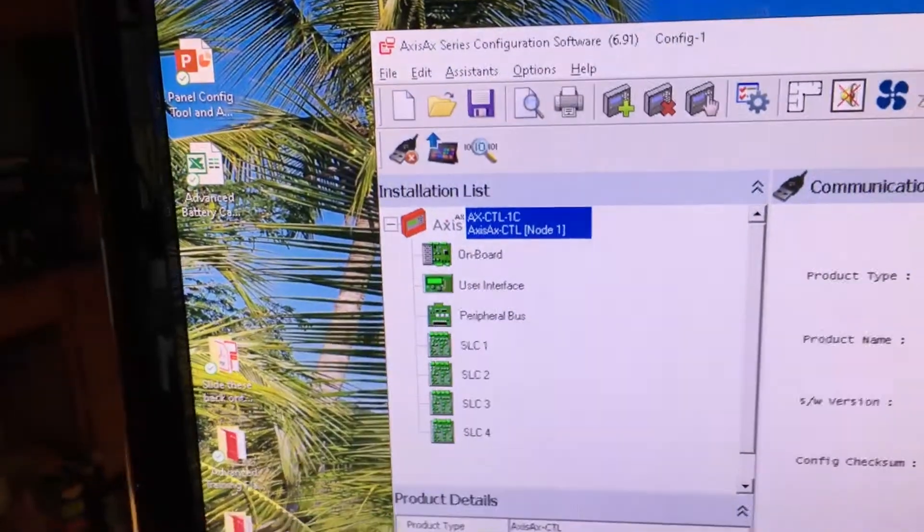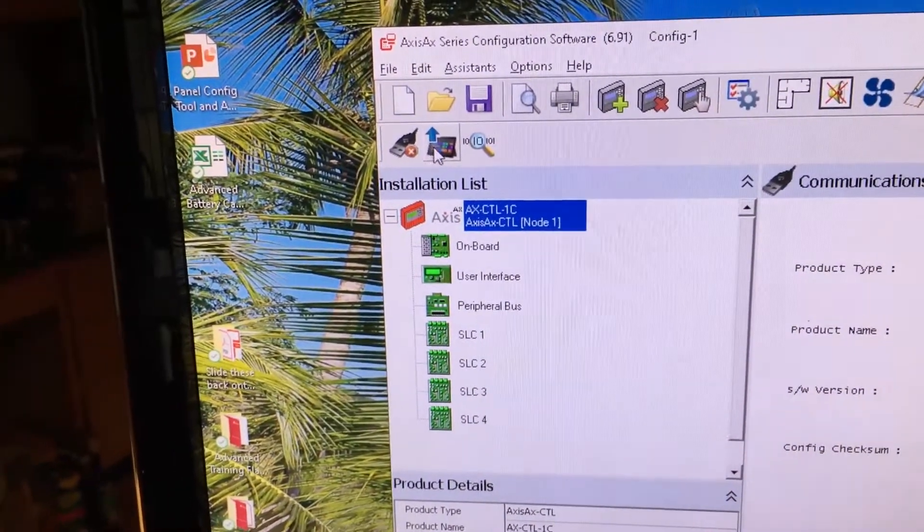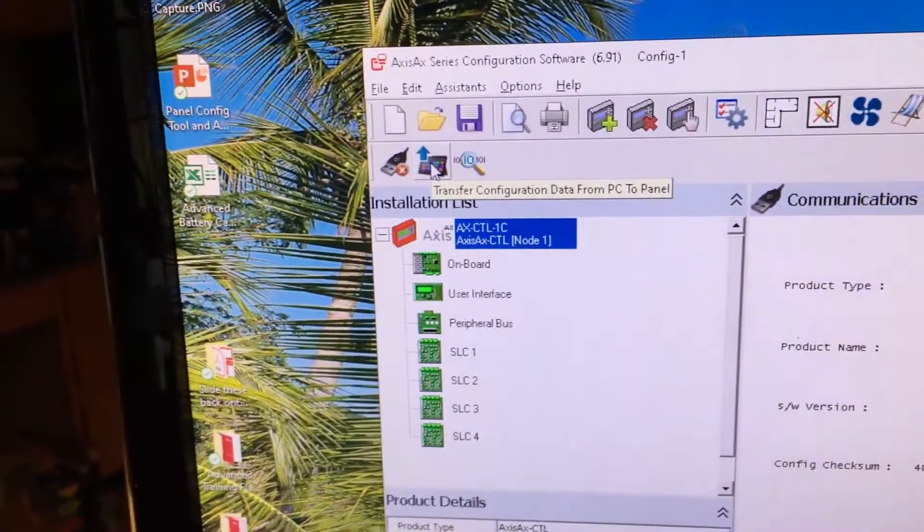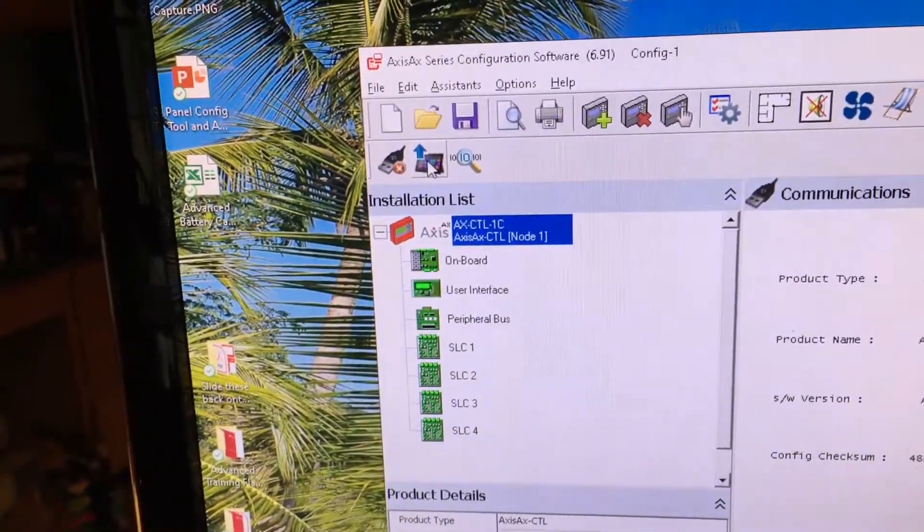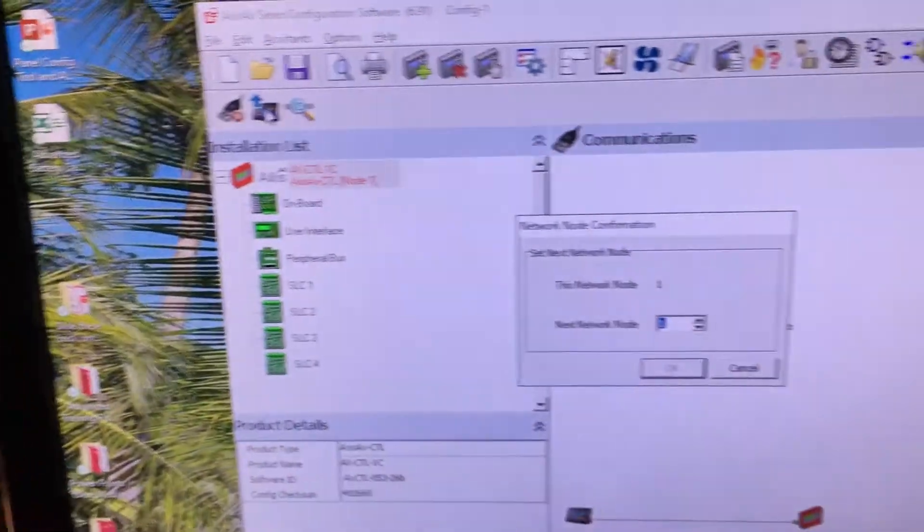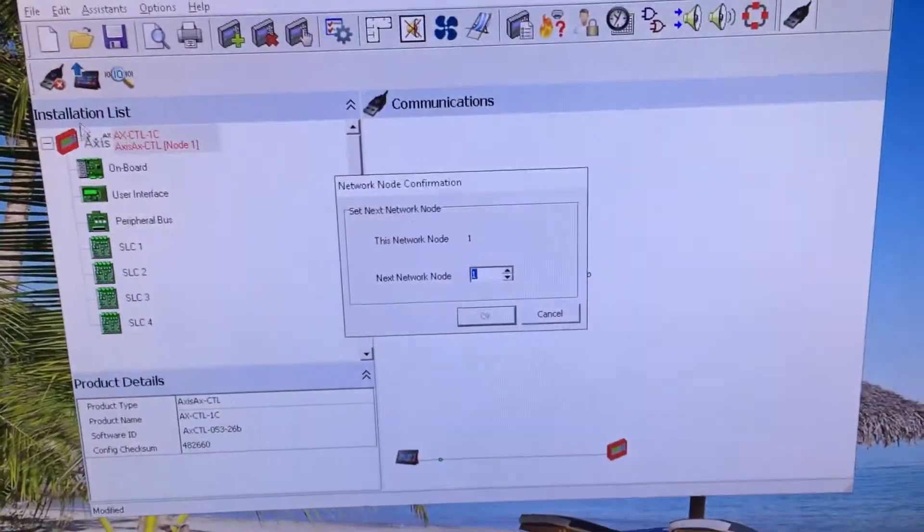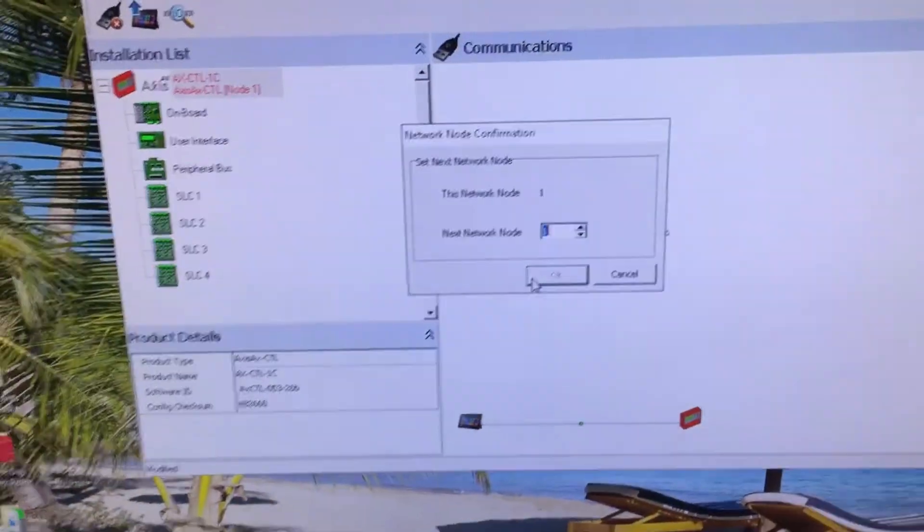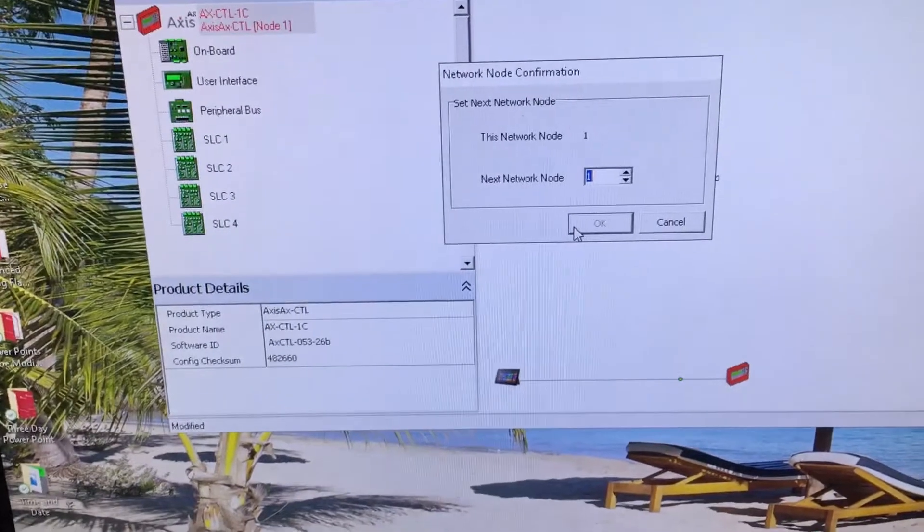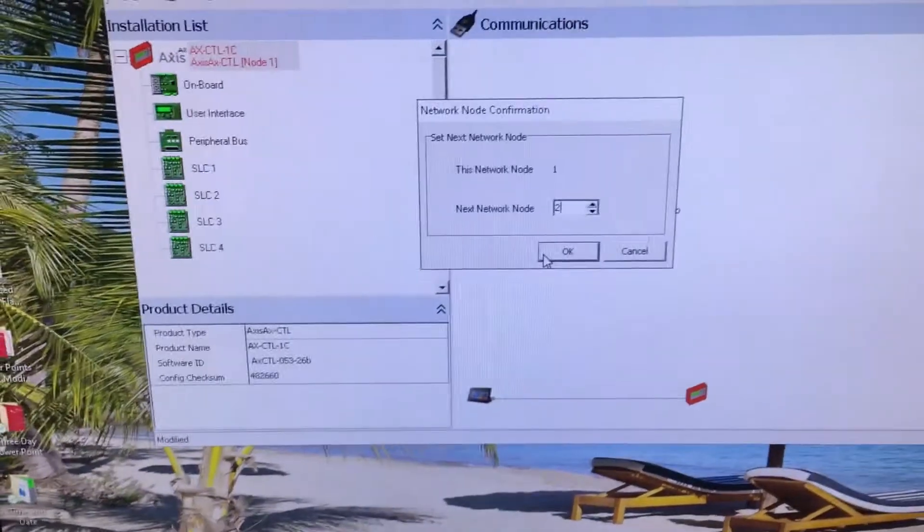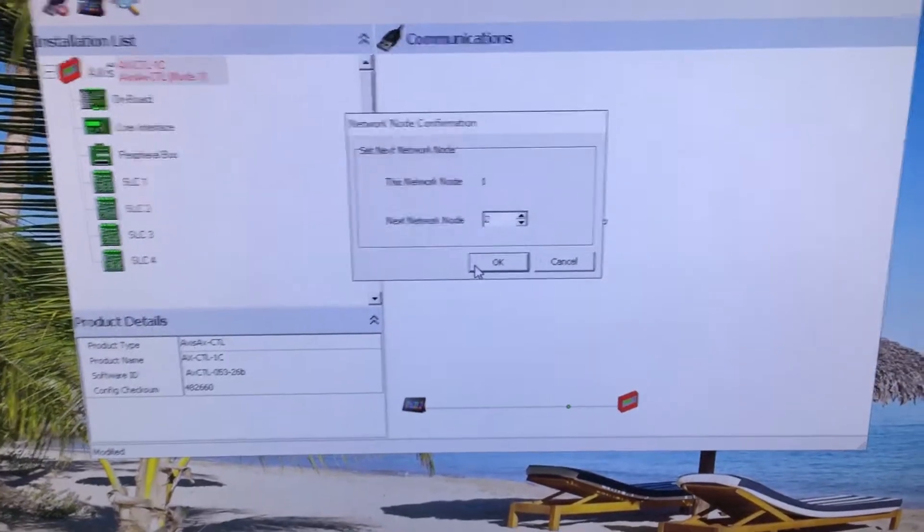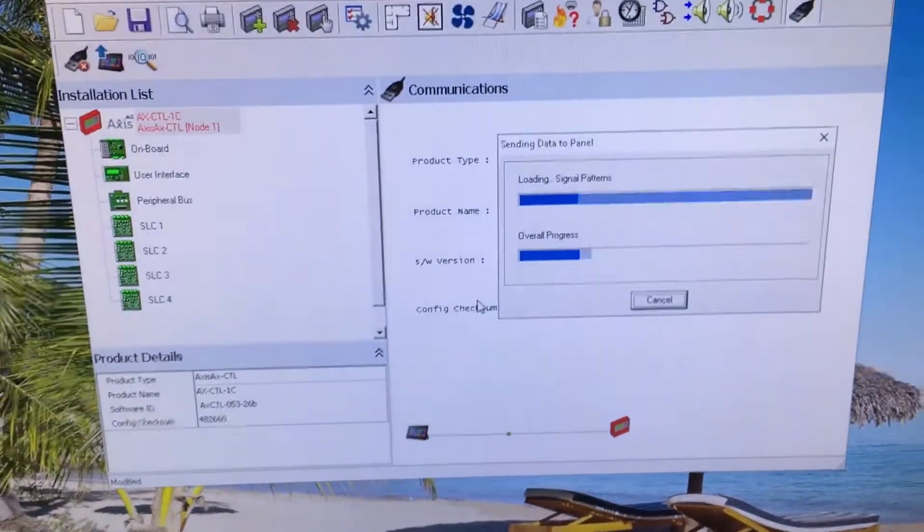We're back at our computer again. What I'm going to do this time is come to the second row of icons. The middle item has a blue arrow on top of a tablet computer, and I will click on that. What's going to happen is it's going to ask me for my node number. This is node number one, the next node is number two. I'm going to change it because I do know that this one is attached to an annunciator. I changed it to a two and I will say okay. All that information now is going into the fire panel.